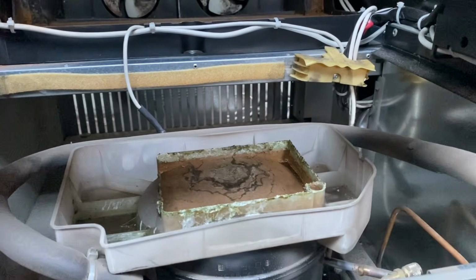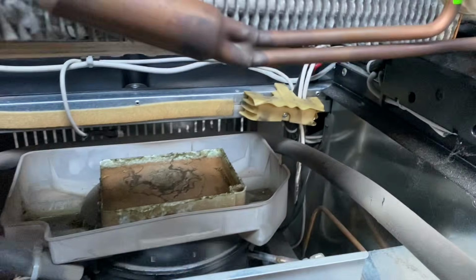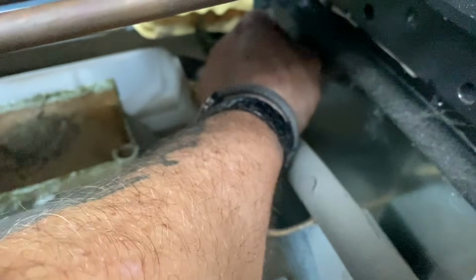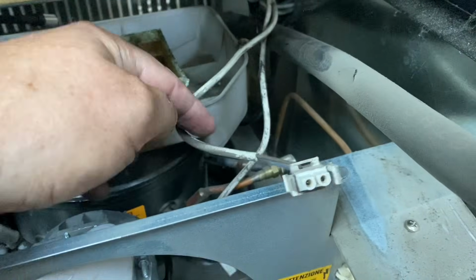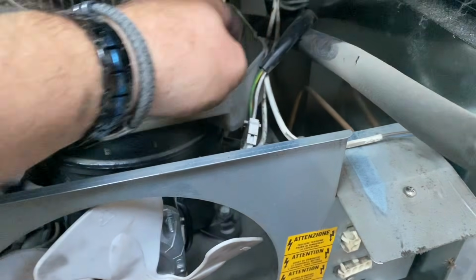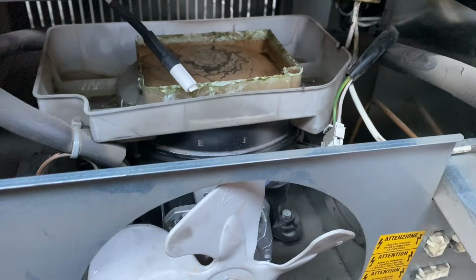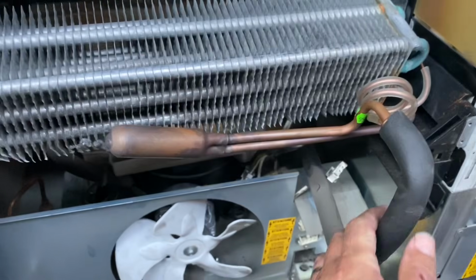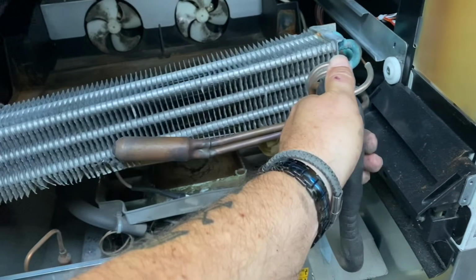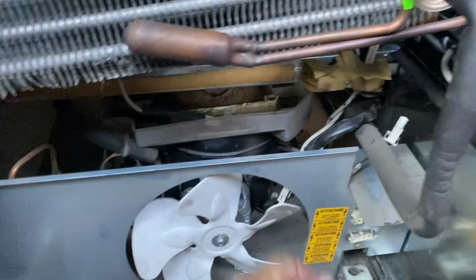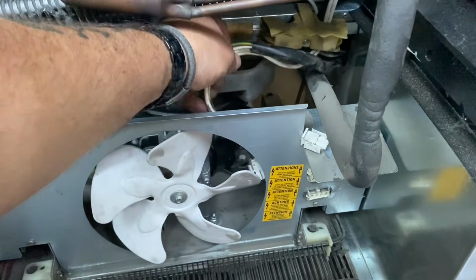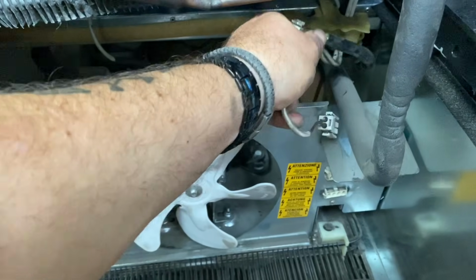So lift the top part of the chiller and press it over the top there, making sure you don't damage any of the drop sensors, and then lay the chiller down and start to push it back in. Every now and again you need to kind of pull the wires through, because obviously you need these coming through so we can plug it in, so don't trap them wires behind the chiller if you are pushing the chiller back in. The same goes for the temperature probe as well, because very often, as you can see there with the temperature probe, it looks like it's going inside the chiller. So you need to just make sure every time you push it back a little bit, make sure them wires are coming out and in the right positions.